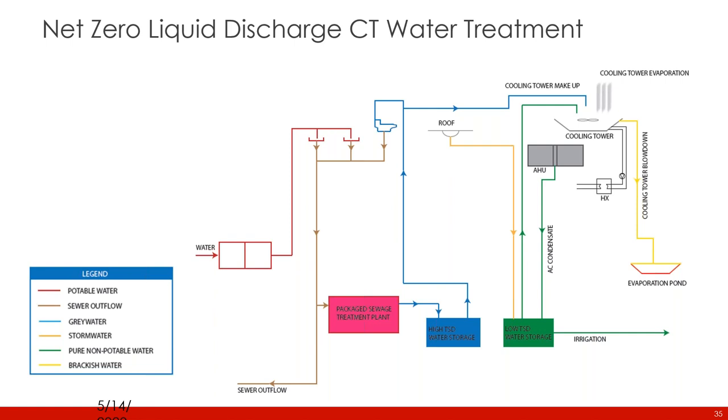Obviously, in cooling tower water that is 100,000 parts per million, you don't have to worry about any kind of antibacteriological or biocidal treatment because nothing will grow in that water at all, ever. So don't have to worry about Legionella in that water, that's for sure. So when you do this, what happens is that you do still have a very small amount of blowdown, but you get rid of it by putting it into an evaporation pond and then harvesting the salts after the water evaporates.